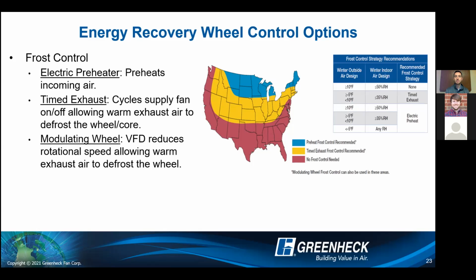There's a big difference between a space that is very dry, maybe 35% or 30% relative humidity coming back, versus a locker room type application where maybe you have 60% relative humidity coming back. There's going to be a lot more buildup of moisture on that wheel. So now we might change the frost control recommendations that we make. This map shows one thing, but obviously the table on the right, it does really depend on your application as well.